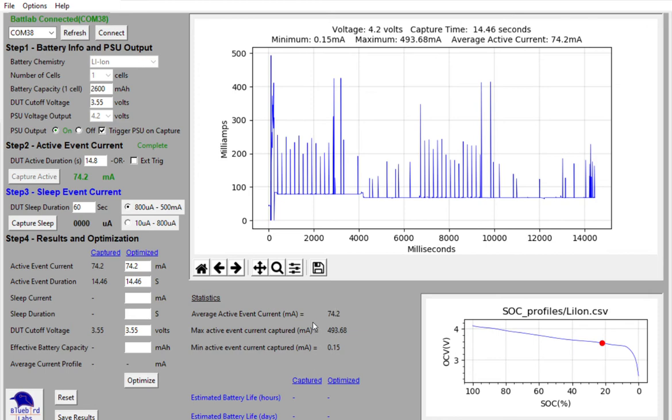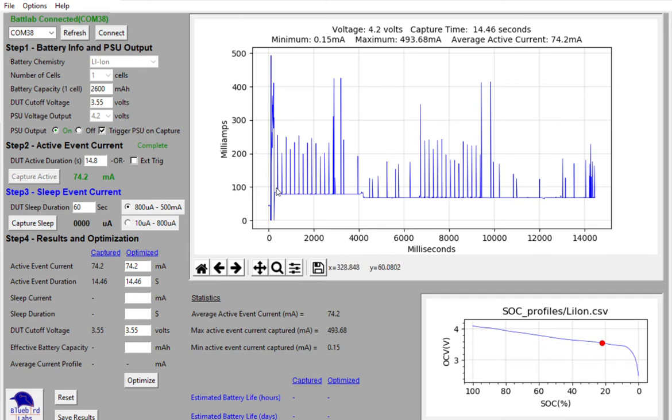The maximum event current captured was about 493 milliamps. And the minimum was about 0.15 basically right when we turned the device on. And some of that may have been some inrush current.